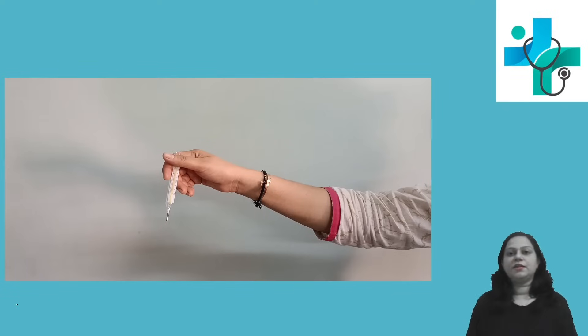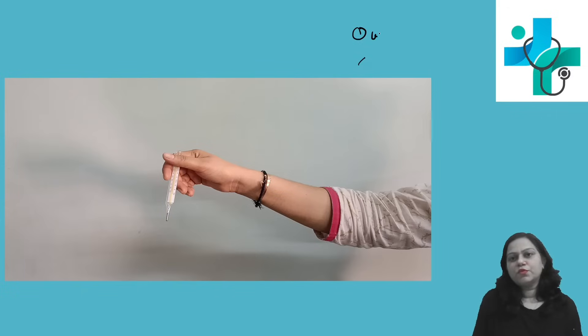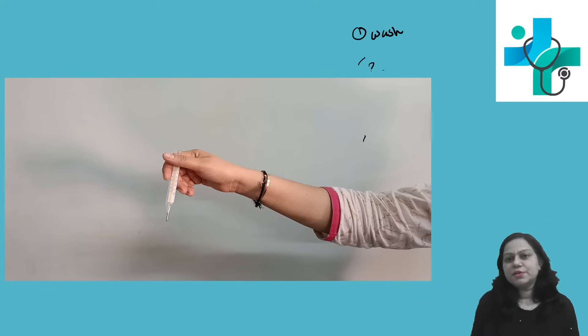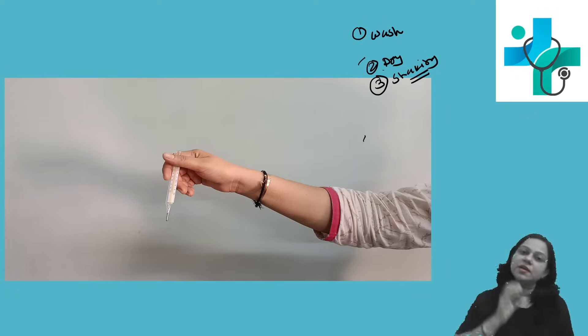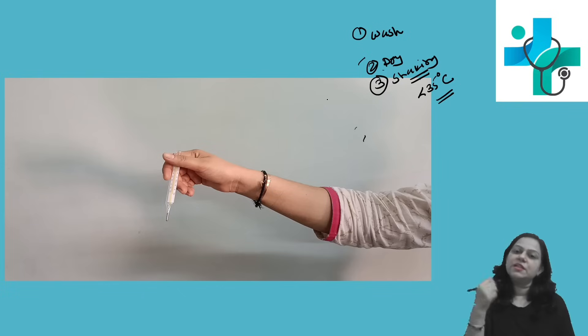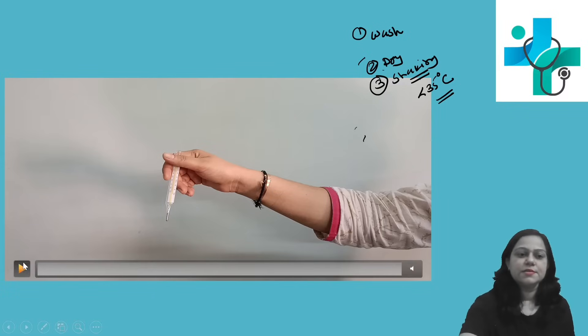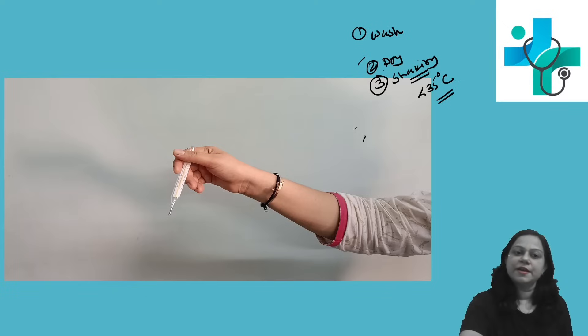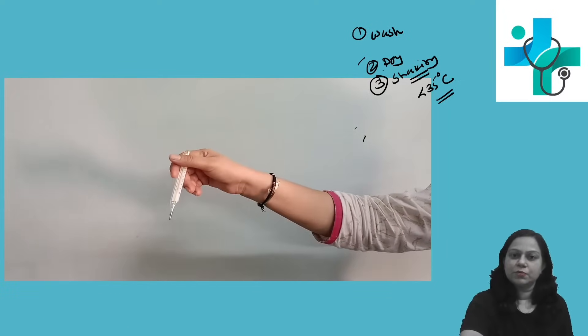Let us understand how to use the clinical thermometer. The steps are: first, wash the bulb of the clinical thermometer in clean water or in antiseptic solution. Second, dry it. Third, by shaking movements of the hand, bring the mercury level down in the thermometer below 35 degree Celsius. You are supposed to move the hand like this — shaking movement — to bring the mercury down below 35 degree Celsius.